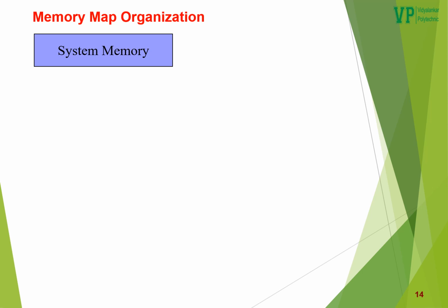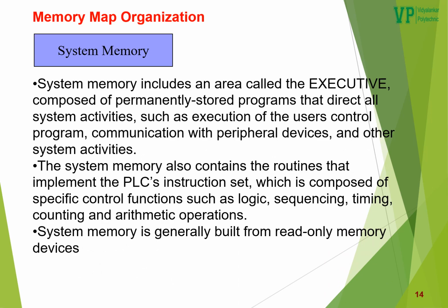Memory of PLC is divided in two parts: system memory and application memory. Let's begin with system memory. Well, system memory includes an area called executive, composed of permanently stored programs that direct all system activities such as execution of the user's control program, communication with peripheral devices, and other system activities. The system memory also contains the routines that implement the PLC's instruction set, which is composed of specific control functions such as logic, sequencing, timing, counting, and arithmetic operations.